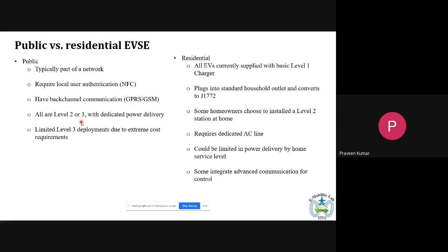Level 3 deployment worldwide today is not on a large extent because of the extreme cost associated with it. Level 3 goes to higher power levels, up to 200 or 300 kilowatts. If a single plug point can deliver 300 kilowatts of power, you can imagine how expensive the entire system becomes, because you need a lot of protection to interface the charger to the grid, and a lot of protection to interface the charger to the vehicle, at both ends, and that adds to the cost.